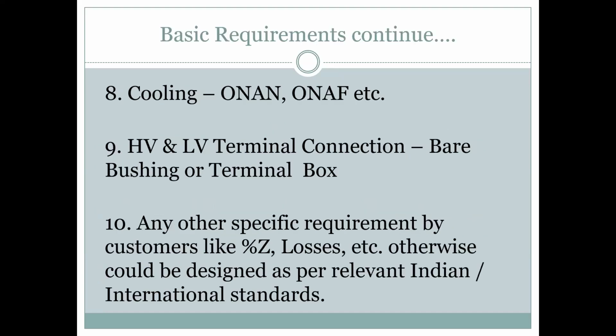Cooling, oil, and then termination. Somebody wants a cable box, somebody wants bare bushing or a terminal box. Any other specific requirement by percentage impedance. This percentage impedance is a very, very important part. It is the resistance plus reactance of the total winding. It basically gives you the short circuit withstand capacity of the transformer. If a dead short circuit takes place in the terminal winding, this percentage impedance will restrict that short circuit current from flowing. Here the tertiary winding also comes into the picture to bypass that load.